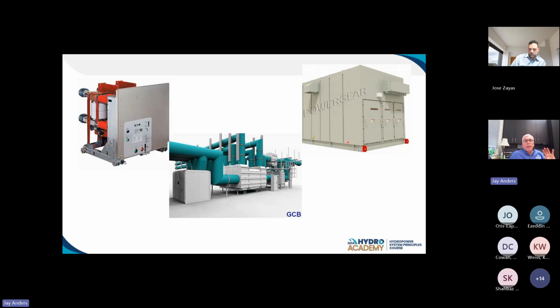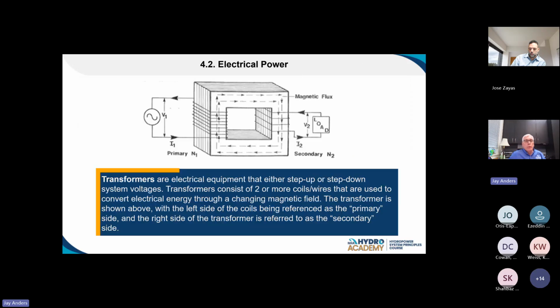When I talked about additive paralleling earlier, this is the breaker that would allow for that to occur. We'd be controlling the speed of my generator and the voltage of my generator to match the other side of this generator breaker, and then it would close, and we could be going online making some power. So generator breakers, again, pretty cool devices.